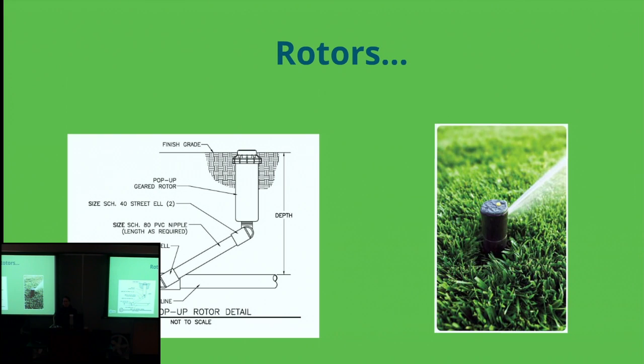So it's important to note on your punch list whether all the heads are perpendicular. Now again, we show the swing joint on the heads. That, of course, you won't see during the water coverage test. You'd see it during installation. Most of the manufacturers today have color-coded nozzles for the radius of the head. So get familiar with the color versus the radius, and when you're out in the field, stick your head down there and look to see that it's the nozzle that you specified. Also, I forgot to say that when you do a water coverage test, you might want to wear waterproof clothing because you will get wet no matter what.